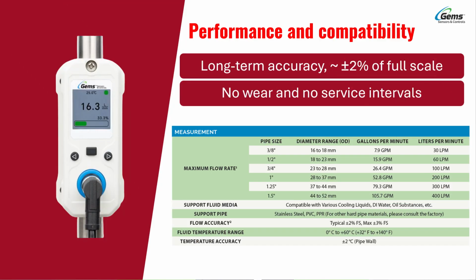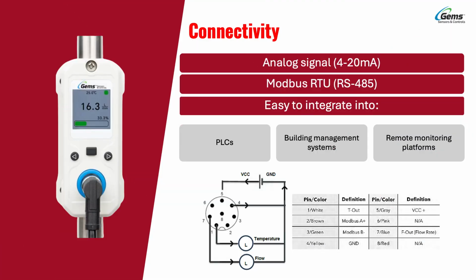With no moving parts, the ultrasonic design delivers long-term accuracy, typically plus or minus 2% of full scale, with no wear and no service intervals. Measure flow on pipes from 3/8 inches to 1.5 inches made of stainless steel, PVC, PPR, and more. The XFT includes both 4 to 20 milliamp analog outputs and RS-485 MODBUS RTU, making it easy to integrate into PLCs, building management systems, or remote monitoring platforms.